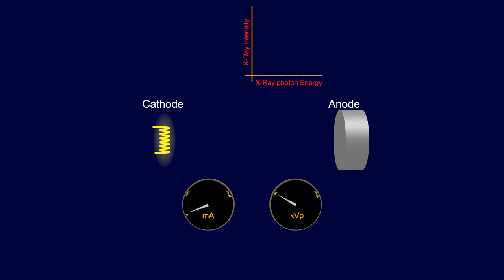This animation represents how increasing KVP with a constant MA impacts how electrons travel from the cathode to the anode. MA, or milliamperage, is the quantity of electrons boiled off of the filament. KVP, or kilovoltage peak, is the speed at which the electrons travel.